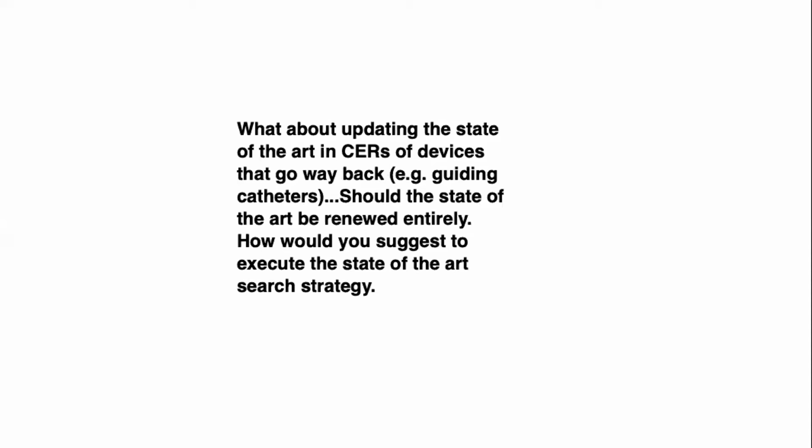So at the end of the state of the art, you have established the safety and performance criteria and the acceptance criteria that you will use throughout the rest of your CER to compare your own device's data to. So the state of the art needs a very thorough look, not just an update, usually.